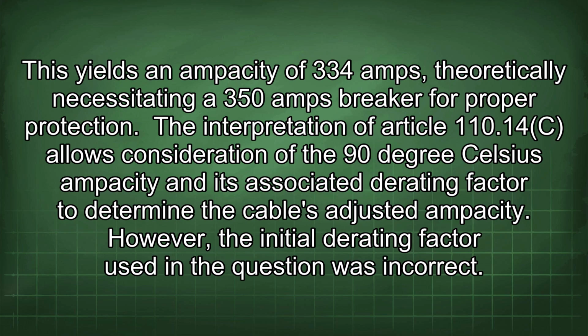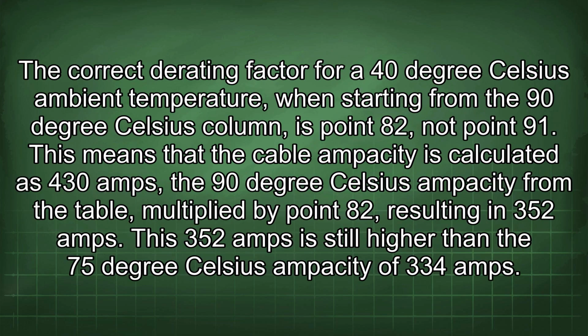The interpretation of Article 110.14(C) allows consideration of the 90 degrees Celsius ampacity and its associated derating factor to determine the cable's adjusted ampacity. However, the initial derating factor used in the question was incorrect. The correct derating factor for a 40 degrees Celsius ambient temperature when starting from the 90 degrees Celsius column is 0.82, not 0.91. This means the cable ampacity is calculated as 430 amps, the 90 degrees Celsius ampacity from the table, multiplied by 0.82, resulting in 352 amps.